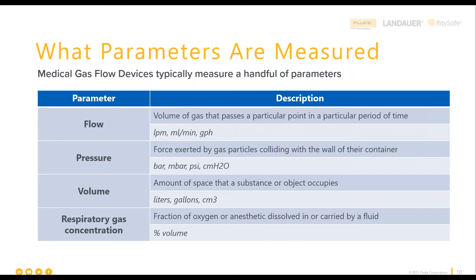Your test device is going to do the measuring — the medical device is either producing the gas or gating and throttling it. So let's jump into flow. Flow is defined as the volume of gas that passes a particular point in a particular period of time. Think about this as runners crossing the finish line of a race: at the beginning when the leaders cross, the flow is lower. But when the slower runners cross together, there's a lot crossing at the same time — that's high flow. Gas flow is measured in liters per minute or milliliters per minute, written as LPM or L/MIN depending on the user's manual.